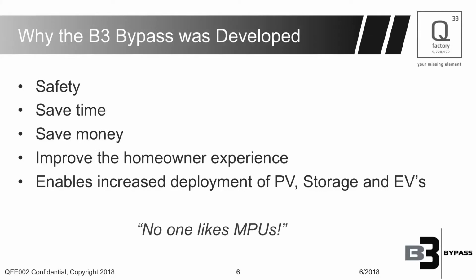Safety is a big issue. The leading cause of home fires is poor connection in the main panel, and we want to address that. The other reason is time. It's a big hassle for installers, an expense for the homeowner, an expense for the installer. We want to improve the customer experience, and we want to help increase the deployment of EVs, storage, and PV to the general marketplace. Nobody likes to do main panel upgrades. When I travel the country and talk to installers and ask, does anybody like doing main panel upgrades? I've had one time where somebody raised their hand, and their whole job was doing main panel upgrades for installers that hated doing it.